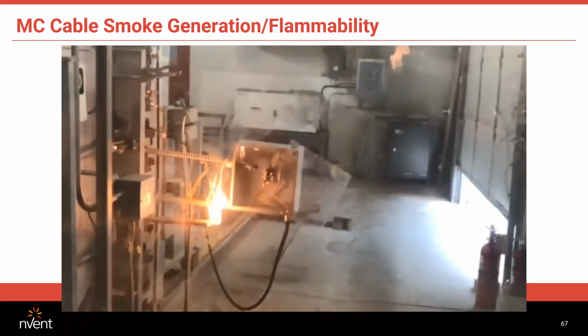And the engineering community is just very concerned about liability, and rightfully so. And MI cable is pretty much all they accept down here. They just don't want to take any chances because crazy things can happen in a fire. And something like this isn't so far-fetched. As I said, when that MC jacketing heats up, there's only 2 directions that smoke can go, left and right, and it's going to get funneled right into a box fitted with some type of arcing device. And you saw what would happen.